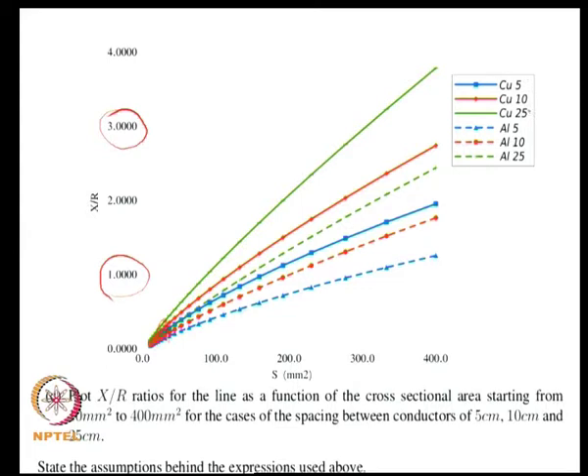The X/R ratio is higher when spacing between conductors is large — for 25 cm spacing you have a higher X/R compared to 5 cm spacing. If you increase the distance between conductors you have more inductance, which is naturally expected. If you want very low inductance you want to bring the conductors closer together and put in a small twist so the wires stay close by, reducing the enclosed area for the flux.